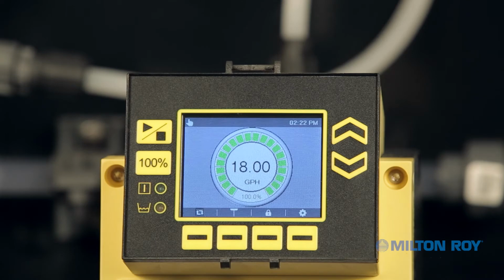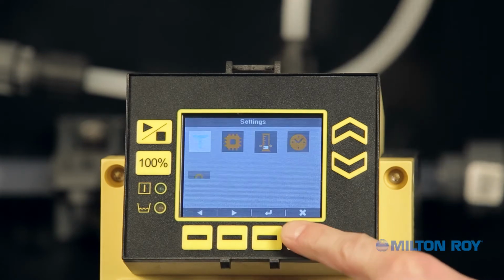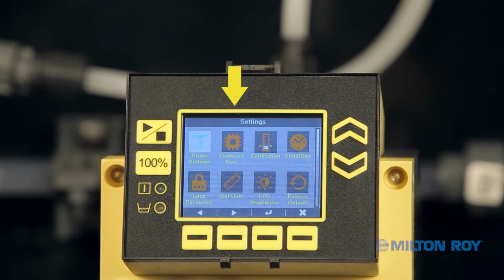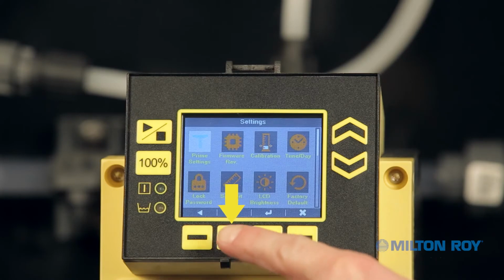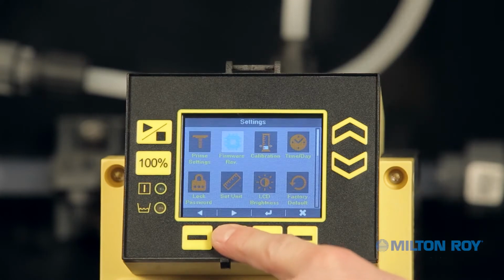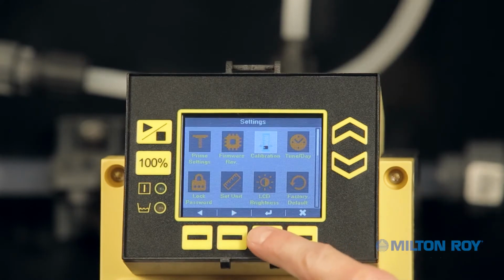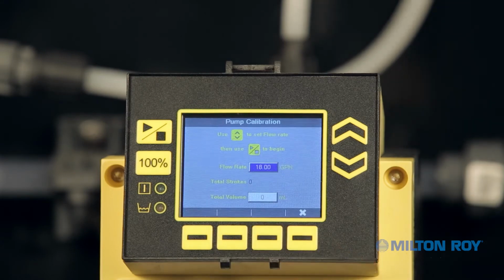Let's get started. Locate the settings icon at the bottom of the screen and press its corresponding button. You should now be in the settings menu. Using the context-sensitive arrow buttons below the lower left of your screen, navigate to the calibration icon and press the context-sensitive button for the Enter icon. You should now be at the pump calibration screen.